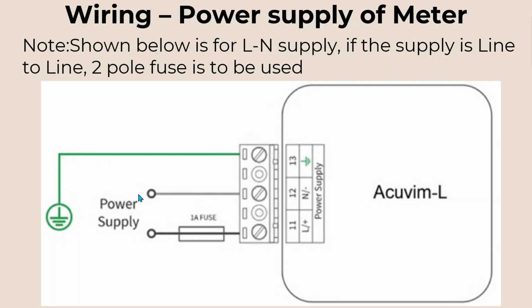This diagram shows how you will connect the power supply of the meter. It can either be derived from the voltage of the meter input, or you can take this supply independent from the voltage input. The advantage of providing a separate supply is that, for example, if it is connected to the UPS, you will always have power even if there is no power in the voltage input. The diagram shows a single fuse because it is assumed to be line here and neutral here. But if your supply is derived from a line-to-line load, for example this is line 1 and this is line 2, you need to provide two-pole fuses for the meter.